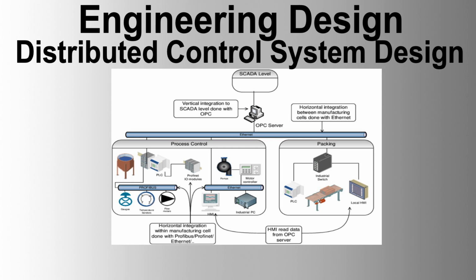Step-by-step installation guides must be provided to ensure proper setup of the system hardware and software. Configuration manuals detailing the setup and customization of the DCS must be included, covering all user configurable parameters. Procedures for integrating the DCS with existing systems and equipment must be documented, ensuring seamless integration and compatibility.